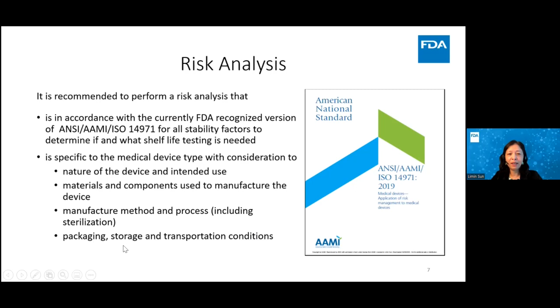So next, I will talk about product shelf life testing. This information is from the guidance document, shelf life of medical device, as well as various device-specific FDA guidance documents or our current thinking. So shelf life testing is conducted to support the proposed expiration date through two types of testing. The first one is evaluation of the packaging integrity for maintaining the device sterility, basically for the device provided sterile by the manufacturers. So this is called a package shelf life testing or stability testing.